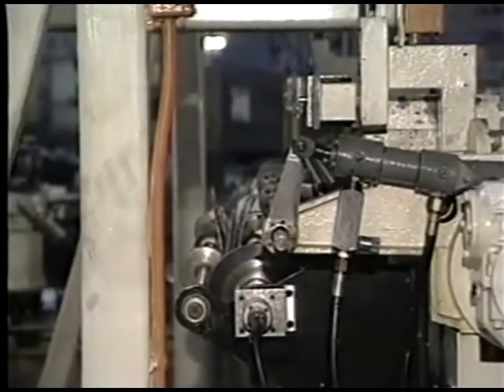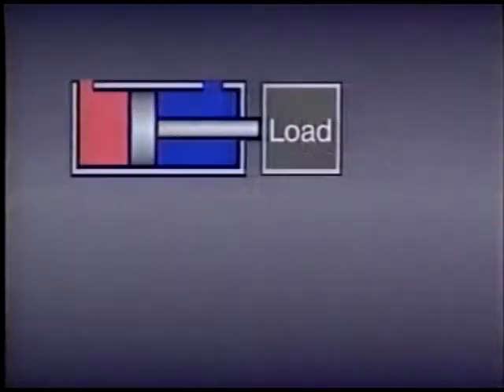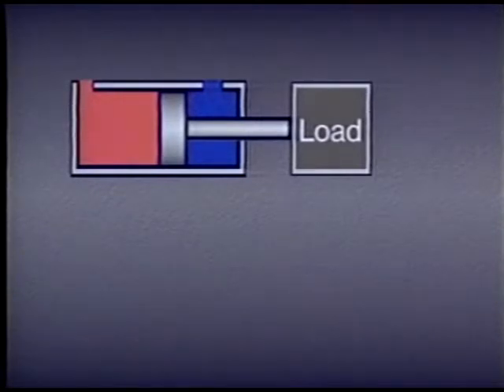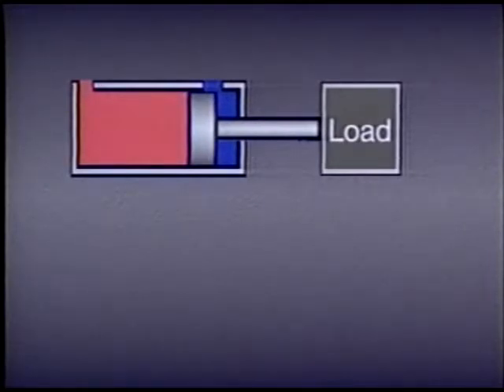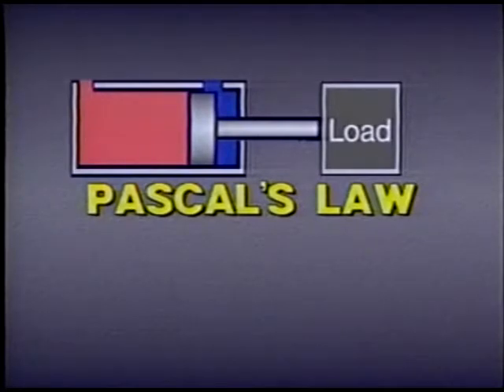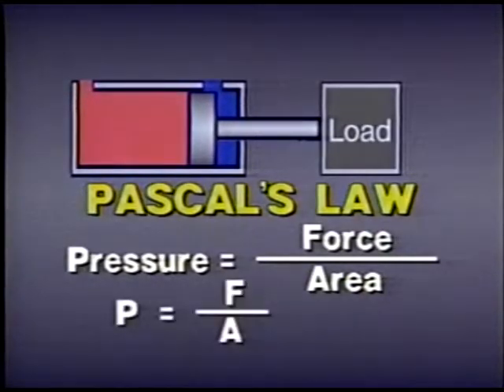In this lesson, we'll examine these basic principles and see how they apply to the operation of all actuators. Let's begin with linear or straight-line actuators. The most common type is the cylinder. When fluid pressure is applied to the piston face, it generates a mechanical force which moves the piston rod and the load in a straight line. How much pressure is required can be calculated using Pascal's law, which states that pressure equals force divided by area — written as P equals F divided by A.